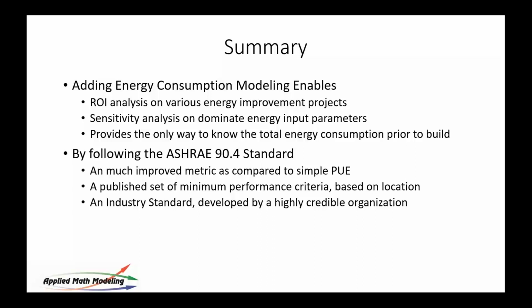We'll do a sample. The other point is, if you're going to measure power, UPSs are a good place to go, right? That's the total, at least going into the IT equipment. But to get the efficiency of the equipment itself, or the UPS itself, you've got to get on the other side of it to the equipment.